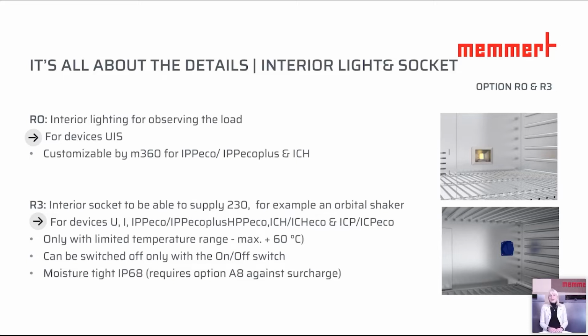Please kindly take note that whenever the unit is equipped with this interior socket, the temperature range has to be reduced, and then we have a maximum temperature of 60 degrees. And that means we also have to go for the option H8, which is a temperature restriction. We can do one socket in a standard, and for our customized solution team, we can even include several sockets in the interior. These sockets are the European standard. Other sockets will also have to be clarified with the M360 team. Let's go on to the next one.